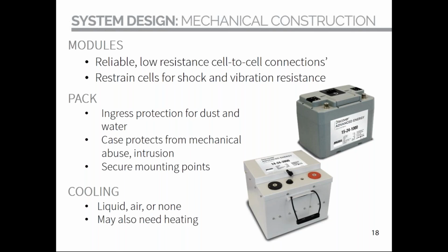Cooling is not only to remove heat from the cells, but also to reduce thermal gradients in the pack. The basic challenge is that cells that run hotter age faster, degrading faster and losing capacity and power, so you want to keep the cells cool. If the whole pack is hot, the whole pack degrades faster. But it's not enough to keep the pack cool overall—you also want to keep temperatures consistent throughout. If some cells run hotter than others, those hot cells age faster, and that uneven aging leads to uneven capacity and resistance, so the weak cells can limit capacity, performance, and life.